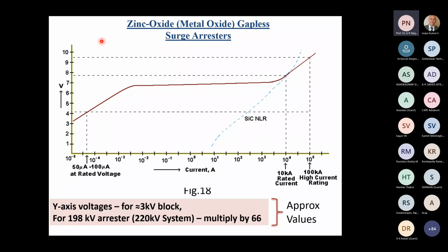In fact, I may in passing mention, there was a time, for example, in the 1940s and 50s, we were finding it very difficult to find a good arrestor which can reduce the voltage to a level acceptable to our transformers. Today, the situation has become just topsy-turvy. Arrestors are available with extremely good protective levels. That means this voltage is very much low. I cannot design a transformer insulation to withstand just this much. If I do that, then it will degrade due to the normal working voltage itself and fail earlier. That's the topsy-turvy case. At one time, it was the arrestor which attracted a lot of attention for improvement. Today, transformer insulation is attracting improvement.